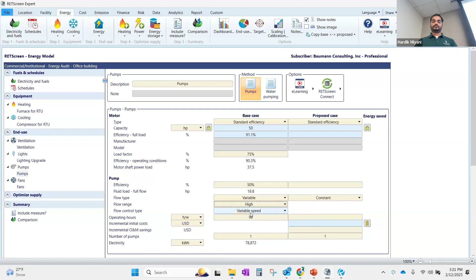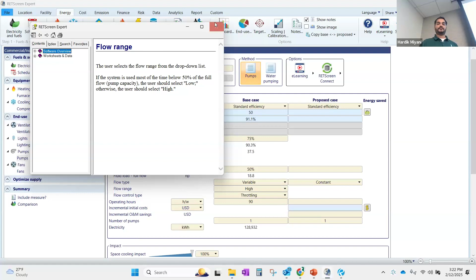So what is the difference between a high and a low flow range? If the system is used most of the time below 50% of the full flow capacity, the user should select a low flow type. Otherwise, it is a high flow type. If a pump is designed to operate at 500 GPM, and it is operating at 100 GPM most of the time, that is where I will select low. And if it is operating above that, it is high, right?